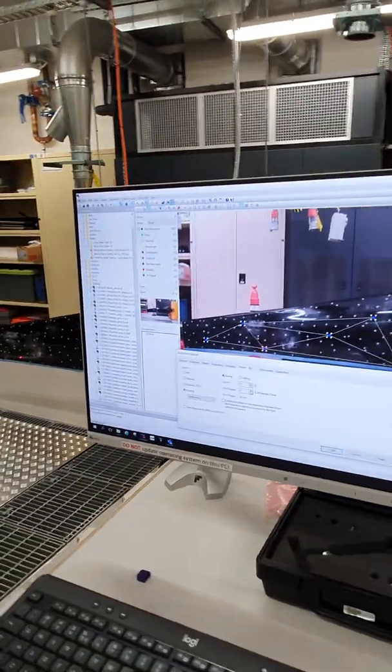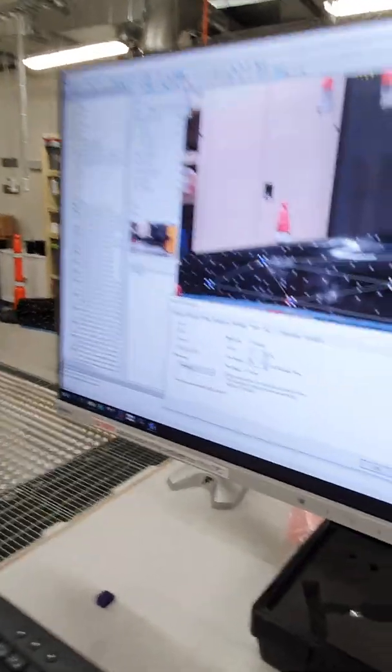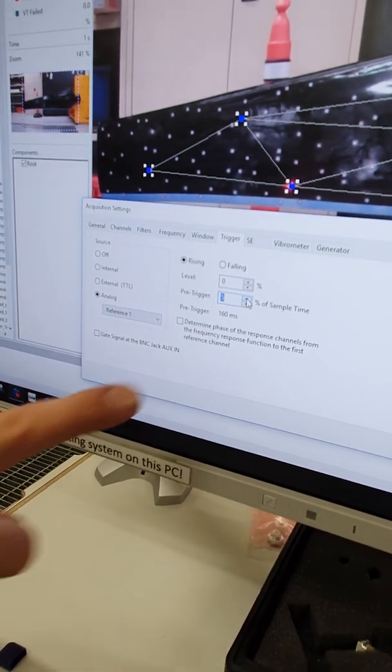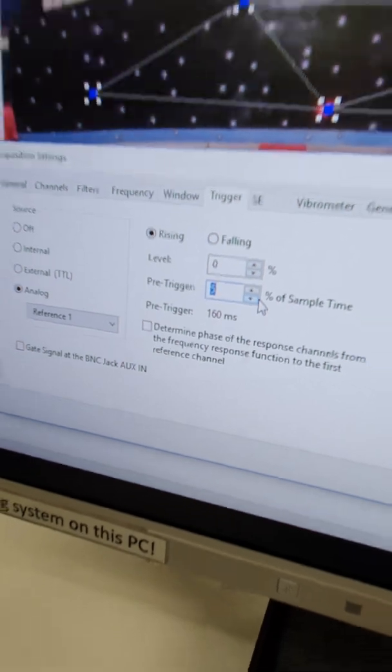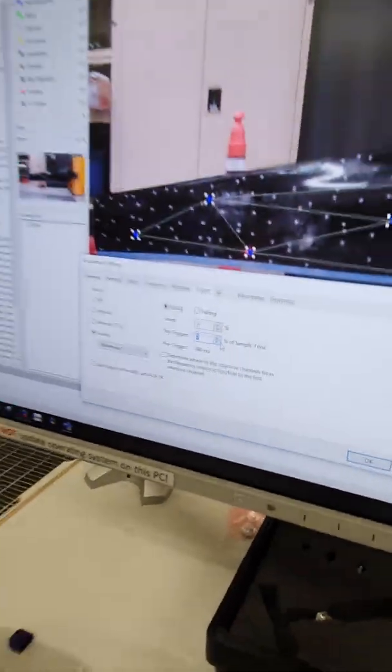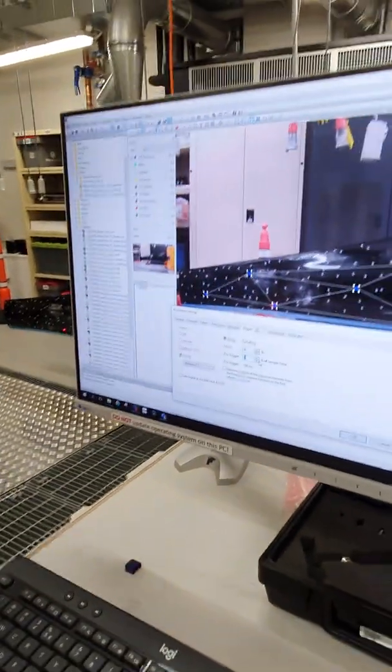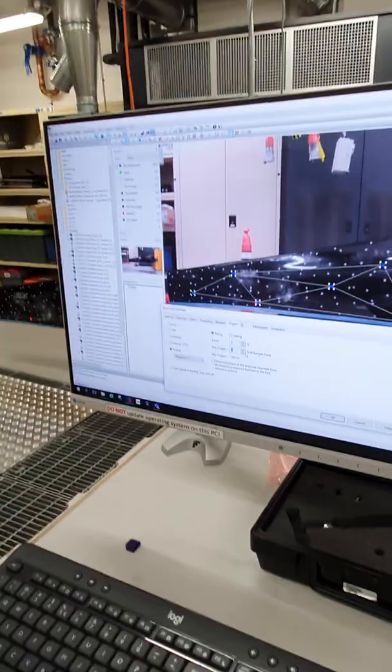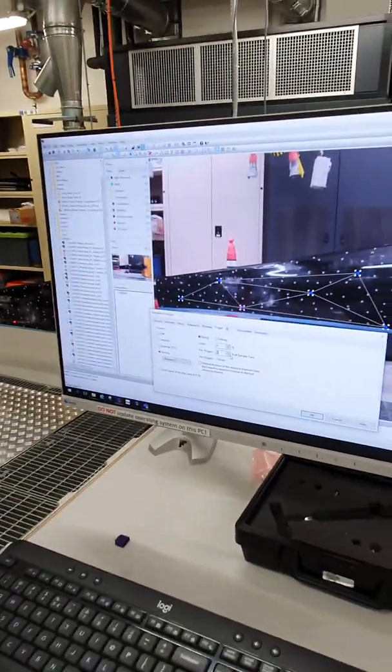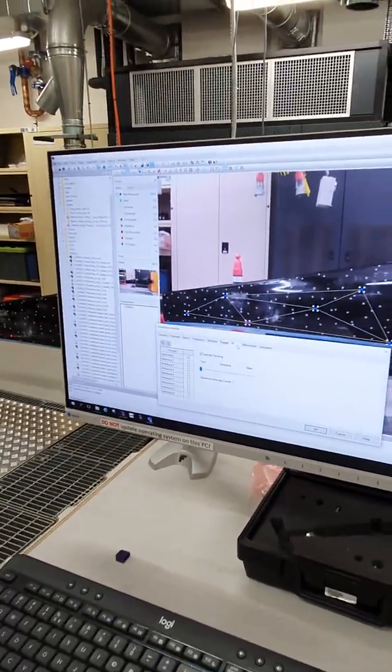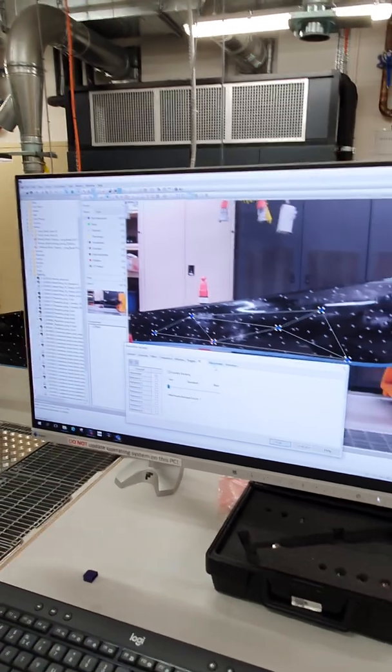And I want to not miss the very front of that, so I'm going to have a pre-trigger that's around five percent of the total sample time, so 160 milliseconds of pre-trigger. So that means when the threshold is overcome with the triggering level, I don't miss that bit at the front because that bit at the start before the trigger level is overcome is still important to me in terms of the calculation.